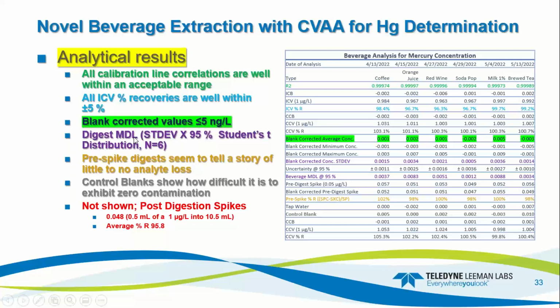The method digest, so standard deviation at 95% student t-value distribution of n equals 6. So that's what these values are right here. So it's the standard deviation of the 7 digested samples. So we have 0.0037. The worst one was 0.008. So again, less than 10 ppt for an MDL within the digest itself.